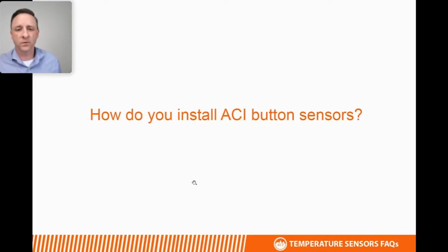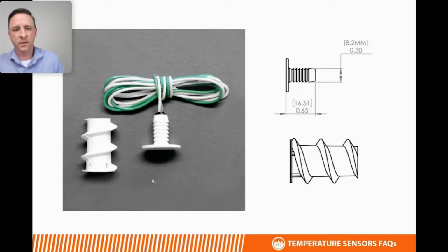How do you install these button sensors? The plastic ones, like you see on the screen here, are shipped with a drywall anchor, like you see here. And so they're commonly installed through drywall, sheetrock, or through ceiling tiles. The metal button sensors are shipped with a lock nut that screws onto the back of the button to hold it in place. So for a similar application, it can be installed through drywall or sheetrock. Sometimes people will install them through a stainless plate, a wall plate or junction box cover, attaching the button sensor to that.